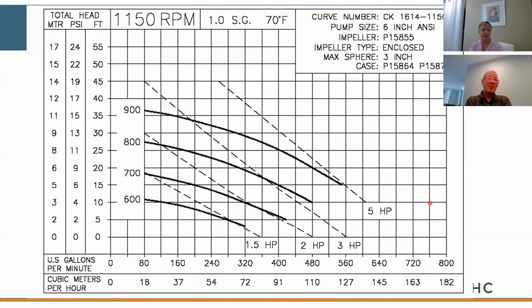Now, if you're used to standard centrifugal pumps, you're used to reading pump curves, and you could select this with software or actually look at a hard curve. On Sump and Sewage, most of these are going to tell you the discharge size of the pump. It's also going to tell you a max sphere or solid size that this pump can handle. So in this case, this is a 6-inch discharge. The pump can pass 3-inch solids. Okay.